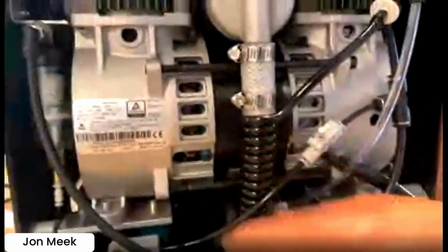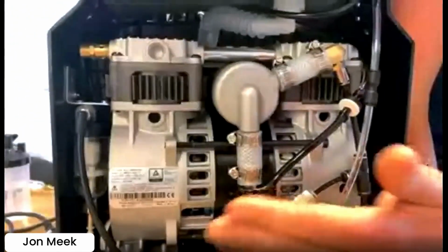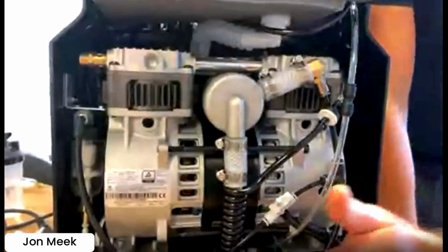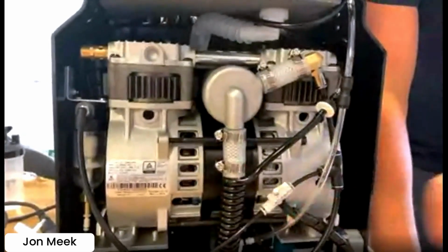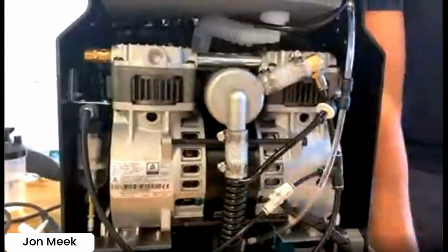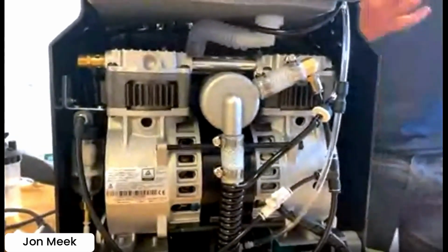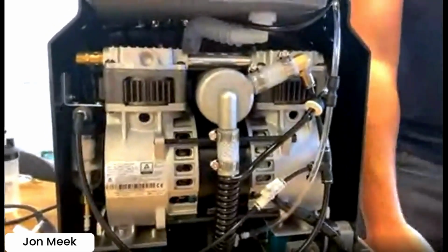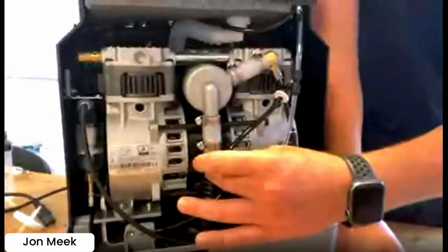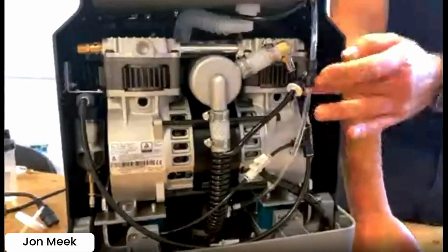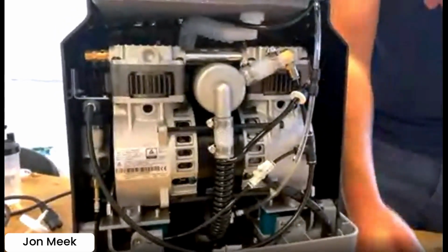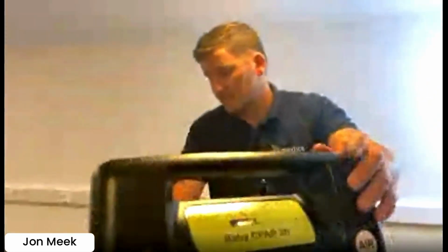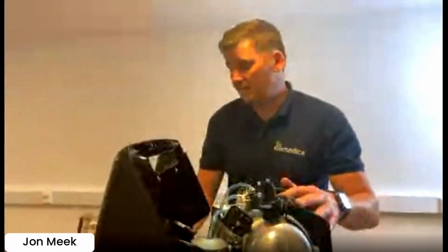And this is what we do here. So there's a coil around a metal pipe which is warmed from the compressor. So we're using these coils as they spin around, letting the air through. And what's happening is it's warming the oxygen, because the oxygen is cold with no moisture. Obviously, we want to ensure we warm the oxygen as well. So it's warming it and then throwing it back through a non-return valve. And that goes directly all the way to your flow meter on the front. So that is the CPAP side.